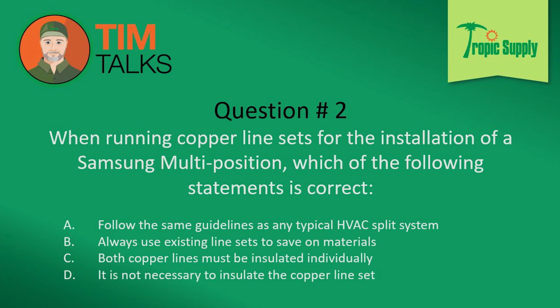Okay, question 2. When running copper line sets for the installation of a Samsung multi-position, which of the following statements is correct? A, follow the same guidelines as any typical HVAC split system. B, always use existing line sets to save on materials. C, both copper lines must be insulated individually. D, it is not necessary to insulate the copper line set.